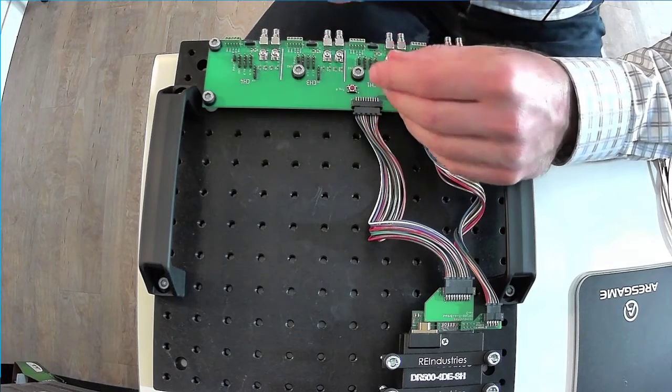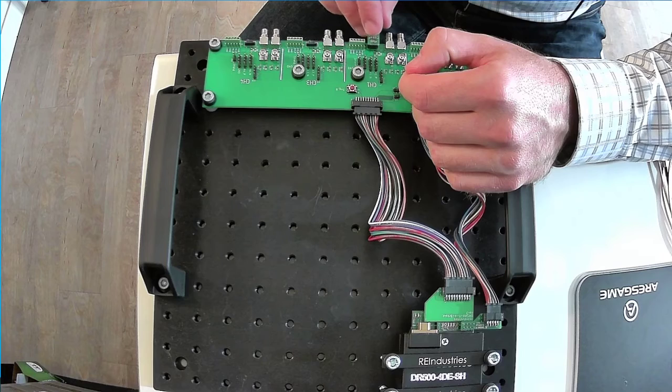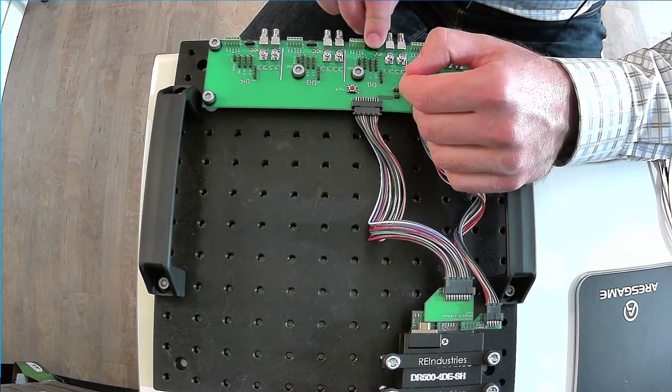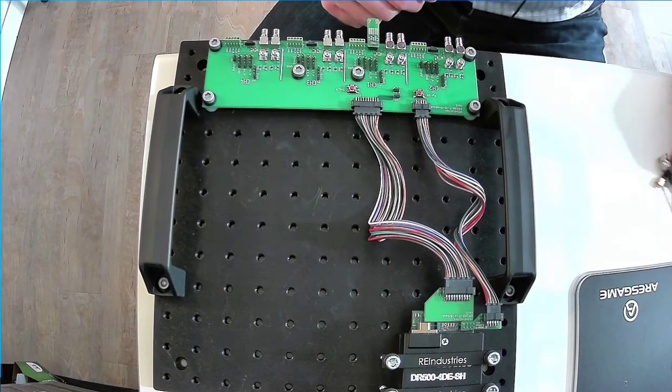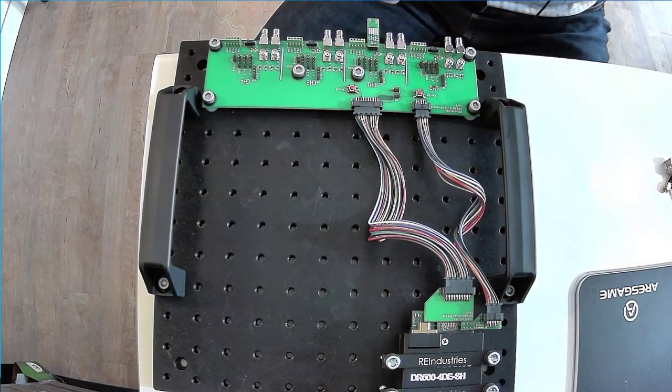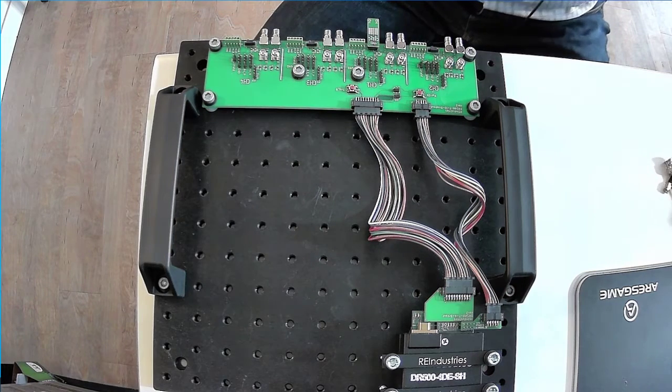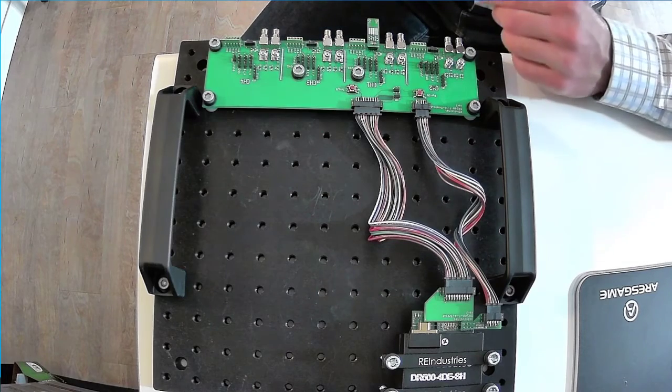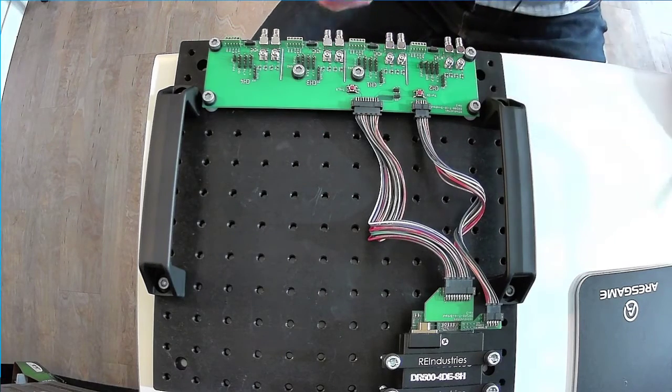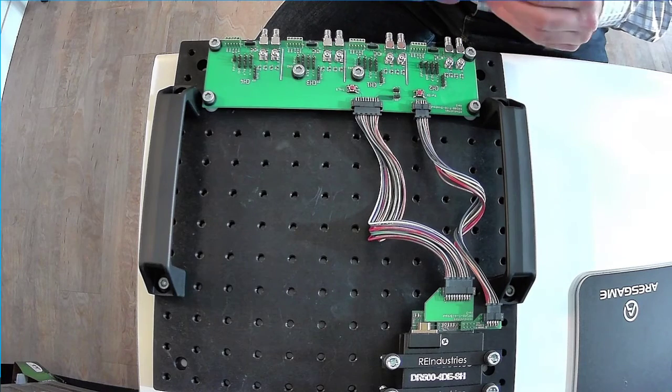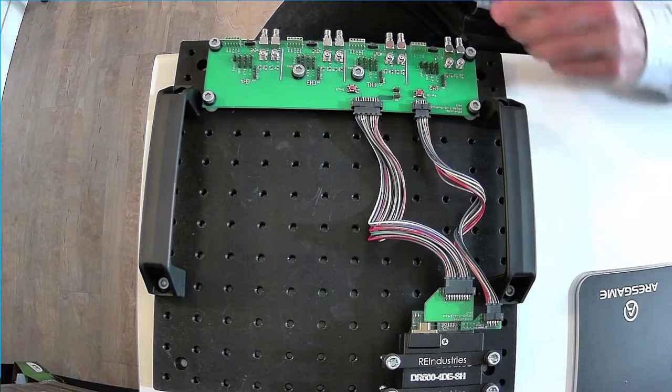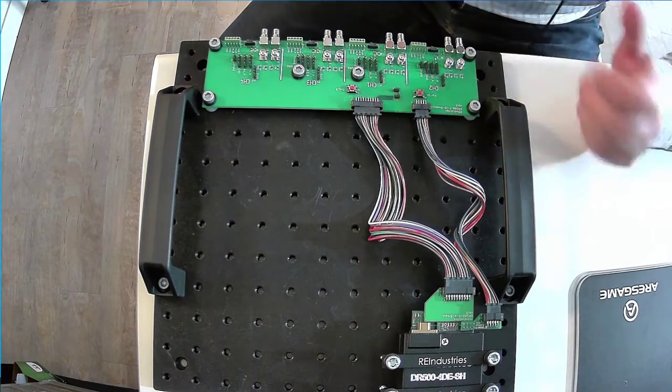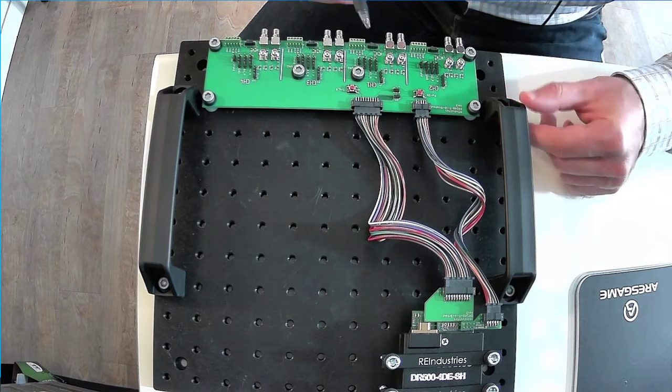So what's really nice is once the accelerometers are terminated for lab use and non-flight testing, this just plugs in. It's a very clean, reliable approach. And it removes the headache of working with extremely delicate small wires from the accelerometer cable harness. So the cable would run out of here. We'll have a video to cover this in more detail. And you can find these cards on our website as well. But that's the purpose of this connector. It's not required, but it's just another option. And it's extremely handy for us, so we want to provide that to customers.